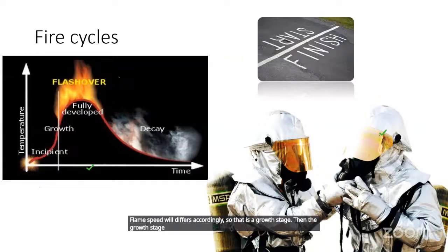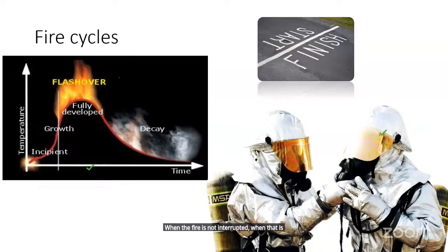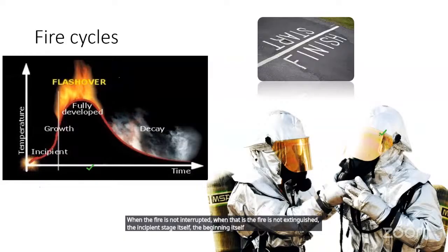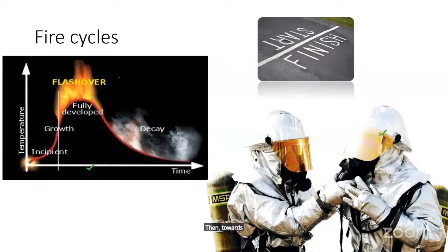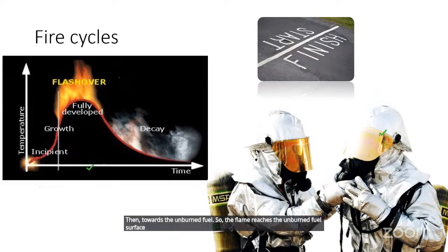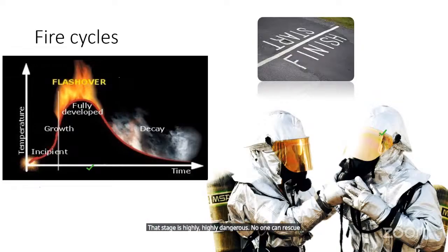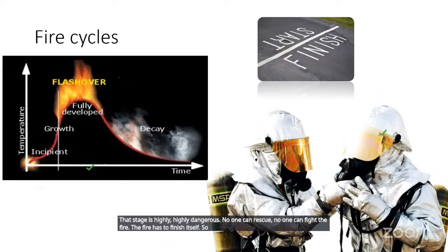Then the growth stage reaches the third stage, called the fully developed stage, where, as we saw in the video, there is a flashover. When a fire starts in a room or at a company and is not extinguished at the incipient stage, the beginning itself, the fire keeps growing towards the unburned fuel. The flame reaches the unburned fuel surface, heats it again, it reaches the fire point, and it catches again. Then the flame size increases like anything. That is called the flashover stage. The entire fuel available in a building starts burning at the same time. That stage is highly, highly dangerous. No one can rescue, no one can fight the fire. The fire has to finish itself. Even a building collapse may happen there. So that is a fully developed fire, called the flashover stage.